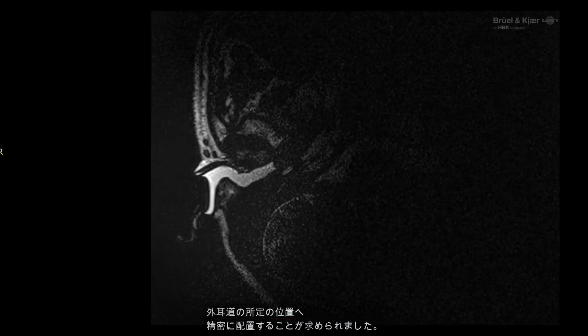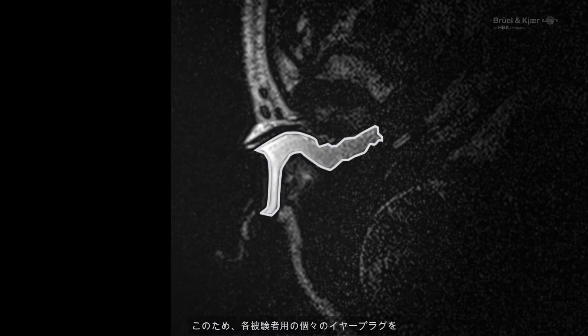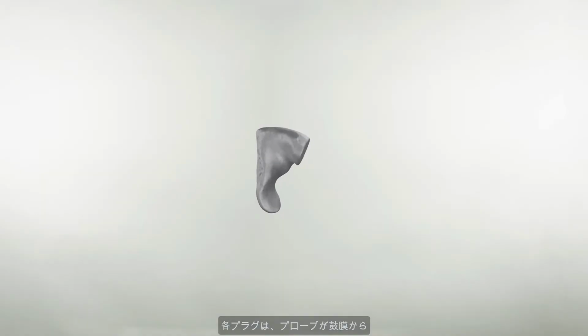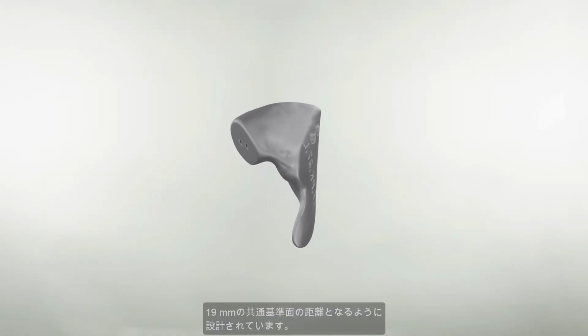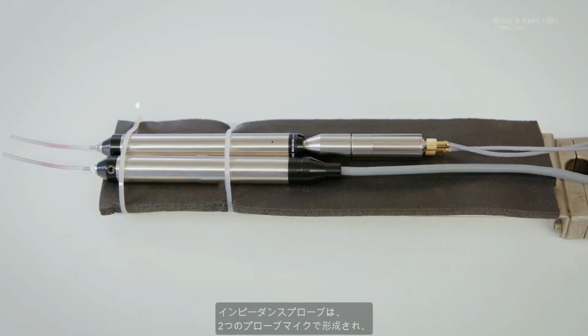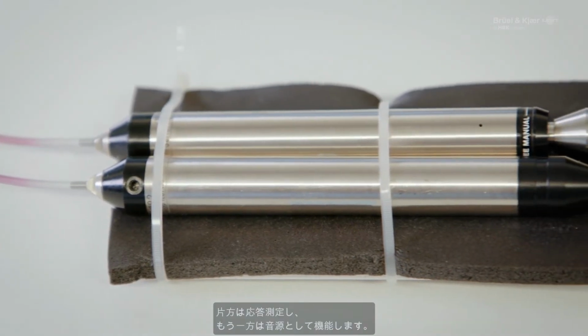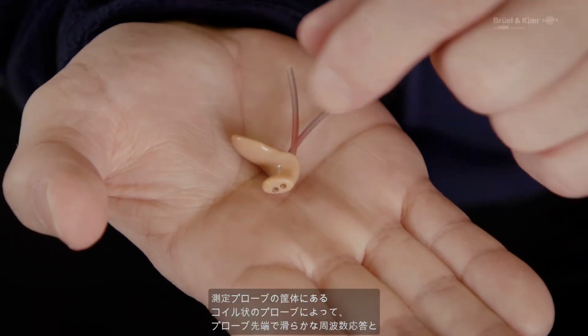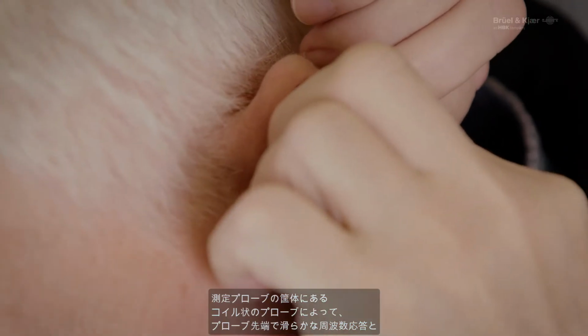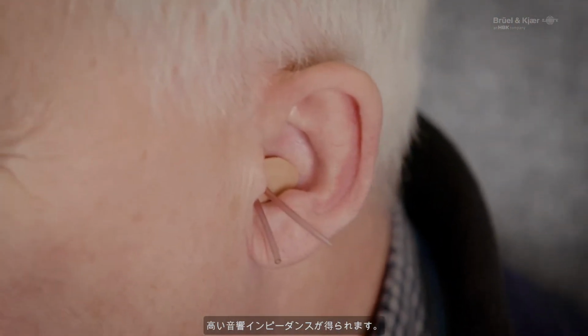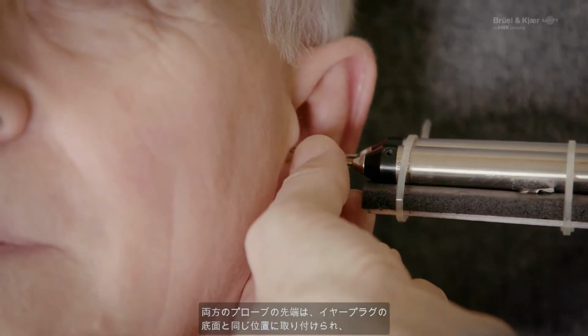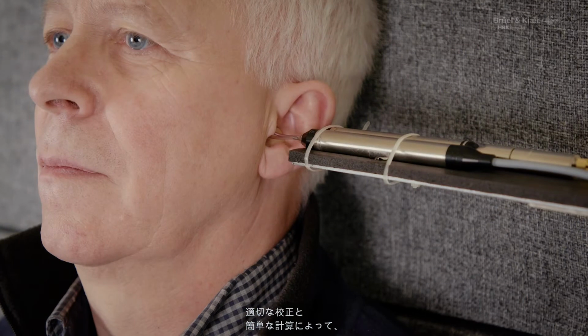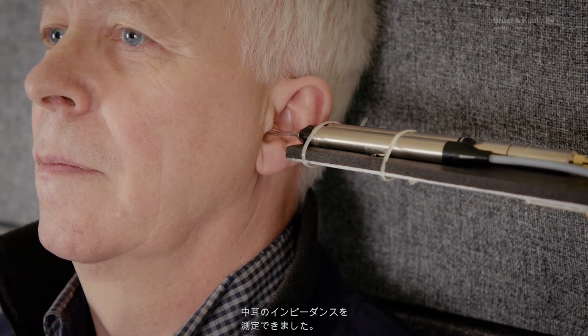This required the application of a specially designed impedance probe which required precise positioning in the ear canal. To do this, individual earplugs for each subject were molded using extracted geometries from the MRI measurements. Each plug was designed to position the probe as close as possible to a common reference plane 19 mm from the eardrum. The impedance probe itself was created using 2 probe microphones, one to measure the response and the other adapted to act as a sound source. A coiled tube in the measuring probe housing provided for a smooth frequency response and a high acoustic impedance at the probe tip. The tips of both probes were mounted flush with the bottom of the ear molds, and with the right calibration and a little math, the impedance of the middle ear could be measured.